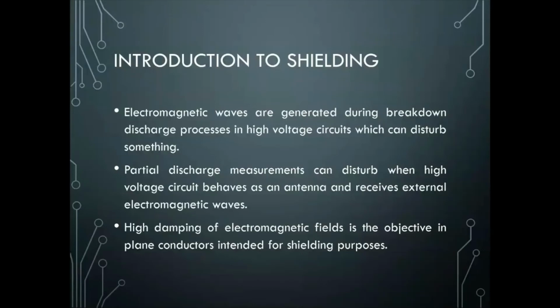Introduction to shielding. Modern high voltage laboratories have to be shielded mainly to avoid electromagnetic disturbances to partial discharge measurement. Electromagnetic waves are generated during the breakdown discharge process in high voltage circuits, which can disturb measurements. Partial discharge measurements can be disturbed when the high voltage circuit behaves as an antenna and receives external electromagnetic waves. High damping of electromagnetic fields is the objective of plane conductors intended for shielding purposes.